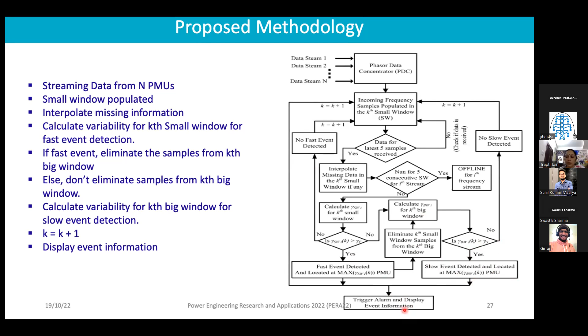We also wanted to take into account that there could be communication delay in the network, so we want to design a method able to tolerate this delay effectively. We observed that typical transmission delay values between PMU and PDC are between 20 to 50 milliseconds, which is about 1 to 2.5 cycles.